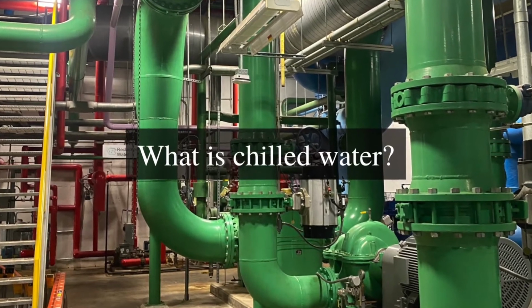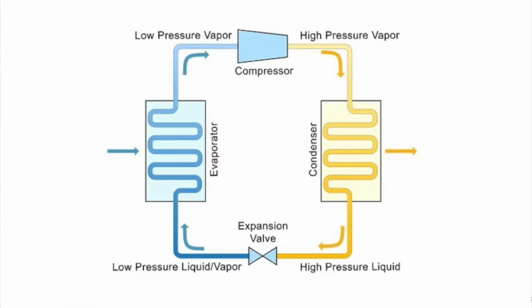So what is chilled water? Chilled water is water that has been deliberately made cooler by means of a refrigeration cycle. The refrigeration cycle takes low-pressure vapor and sends it through a compressor where it comes out high in pressure. From here, it's pushed through a condenser, which turns the vapor into a high-pressure liquid. Then, it travels through the expansion valve, which returns the liquid to low pressure, and the cycle loops from here.